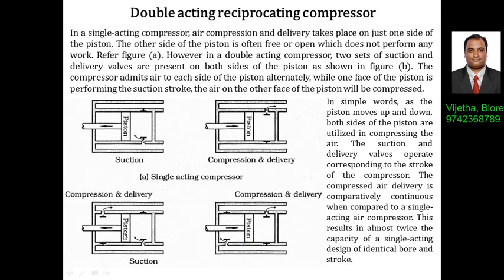In a double acting compressor, two sets of suction and delivery valves are fitted on both sides of the piston. When the piston moves from right to left, suction occurs on the right side while compression and delivery occur on the left side. When the piston moves from left to right, suction occurs on the left side while compression and delivery occur on the right side. For every movement of the piston, a compression process takes place. This is called a double acting reciprocating compressor.